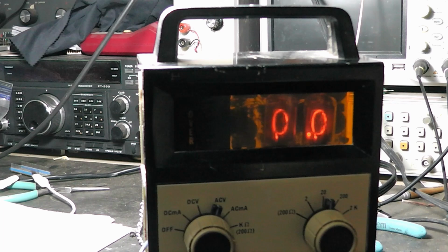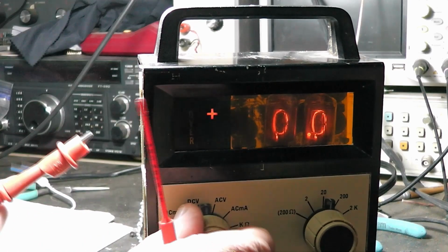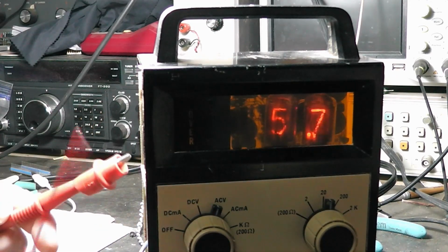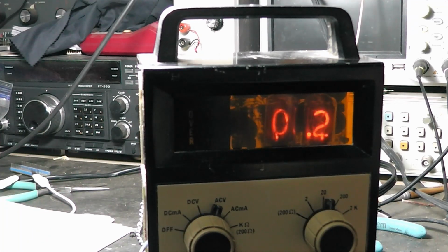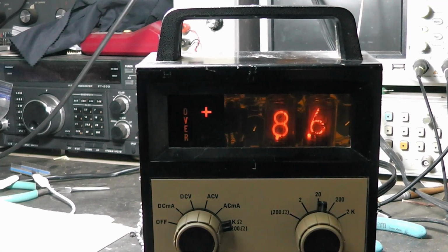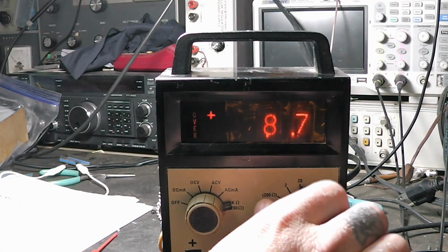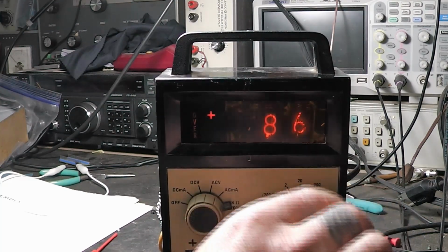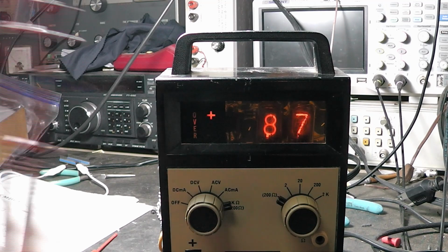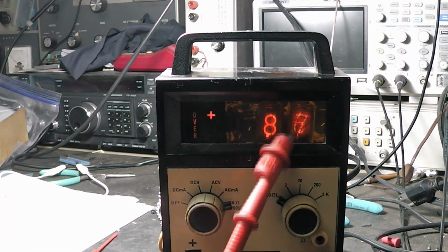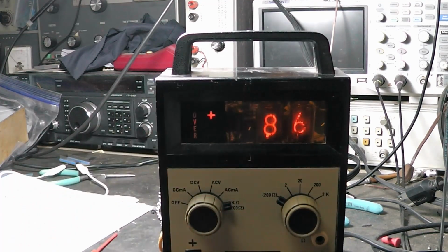And then again, repeat the previous two steps until the correct readouts are obtained in both positions. So you go back to DC volts, get 16.3, go back here, and when that settles down, you're adjusting back and forth, 16.3 like it says in the book, and over 0.0. Okay. And I'm going to move this back to this position here. Okay. And put this on the 200 ohms reading. And here we are with that over and the 0.85, 0.86. As long as it's around in there somewhere, that's the way it's going to read and work properly. Get the most accurate reading.